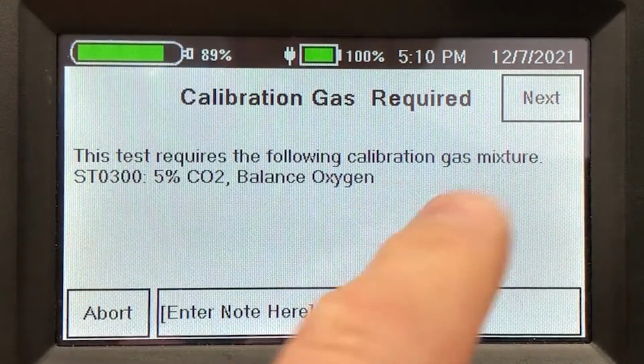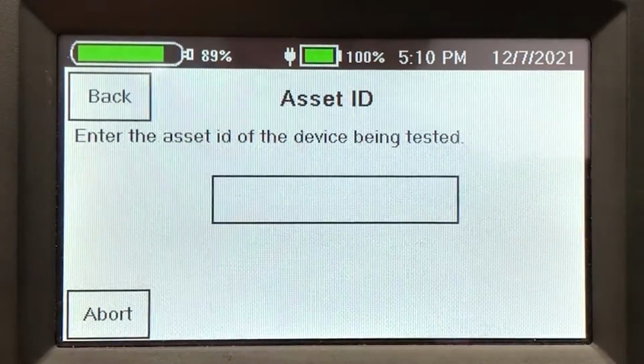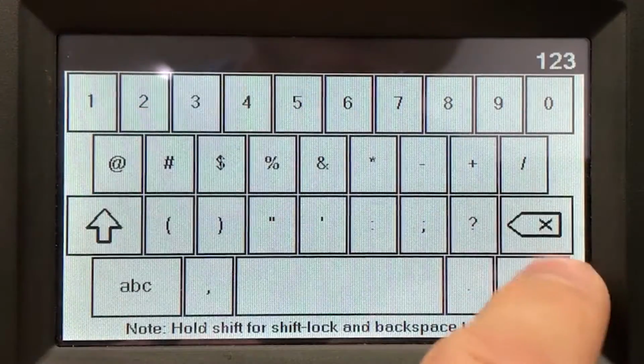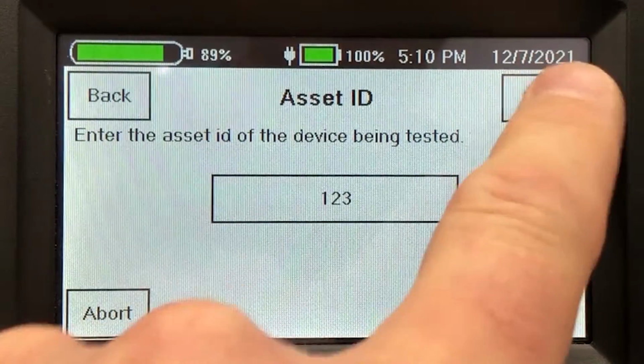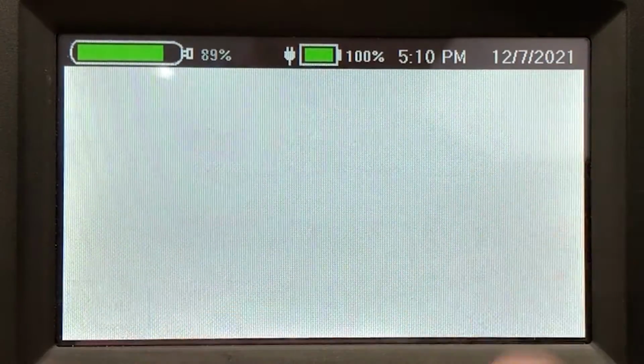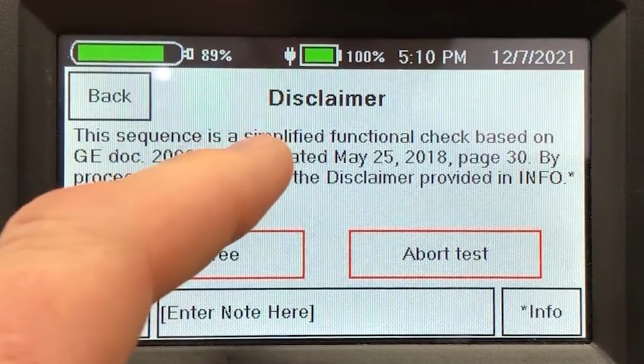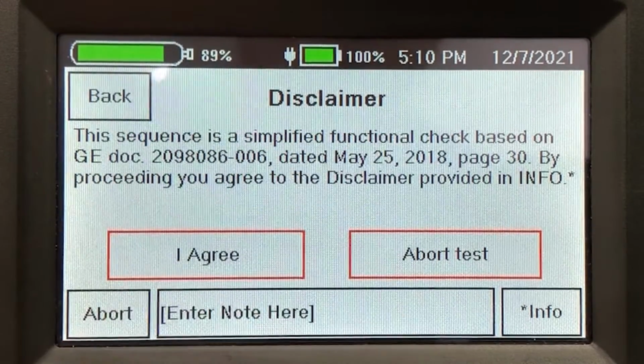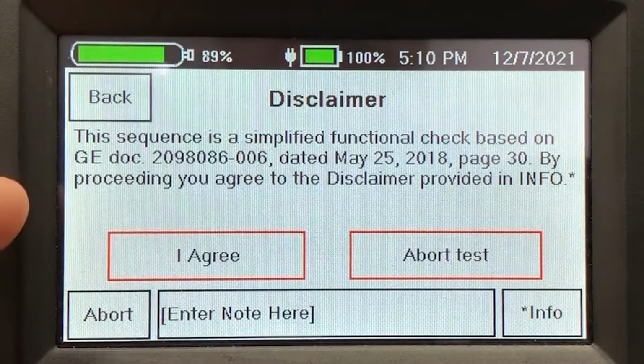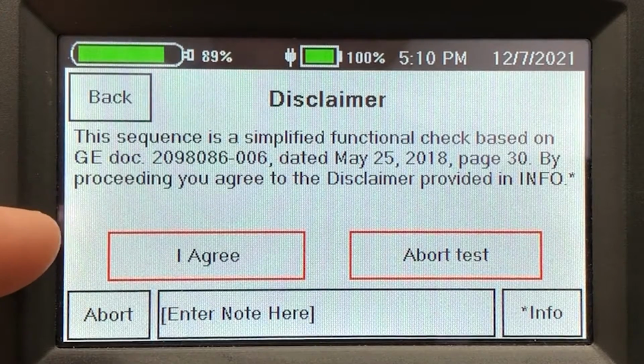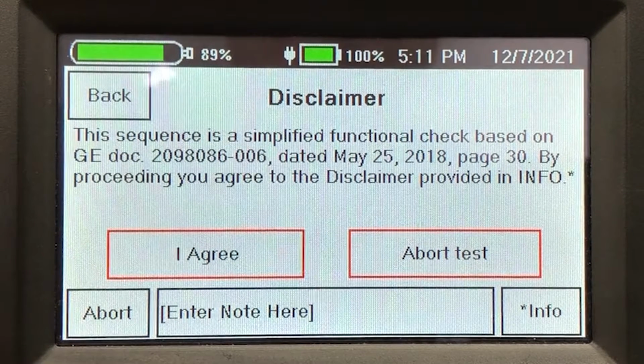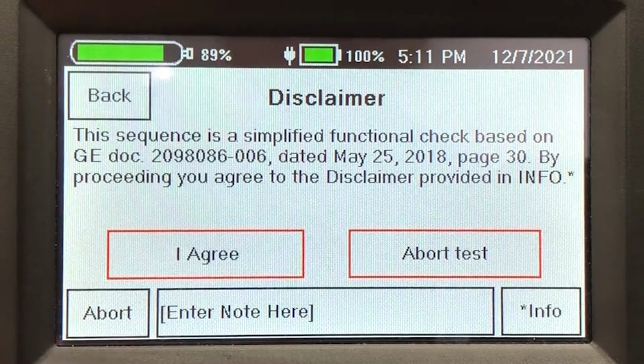This screen tells us what calibration gas is needed for the sequence. And as always, we start by entering the asset ID and the user initials. The disclaimer tells us that it's a simplified functional check and tells us what user manual or service manual the sequence is based on. The disclaimer that we're agreeing to here says that it's our responsibility to make sure that this is the right test sequence for the device we're testing.